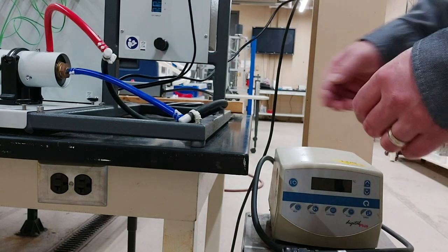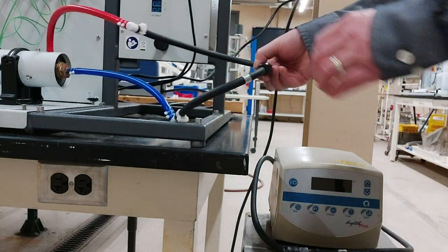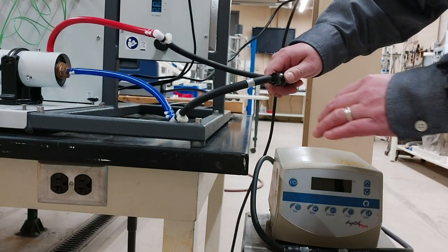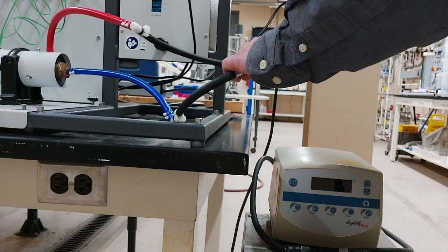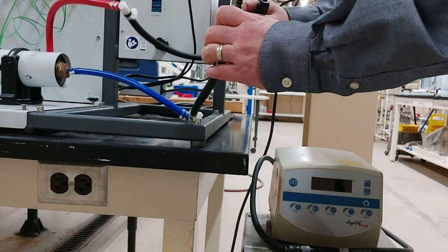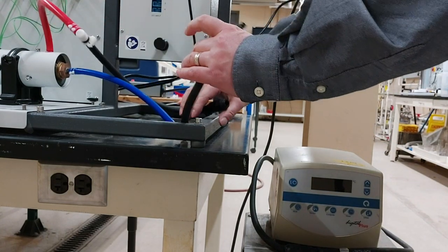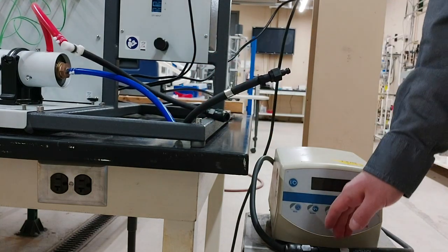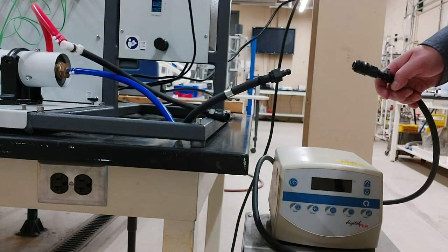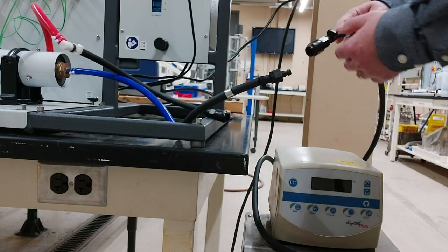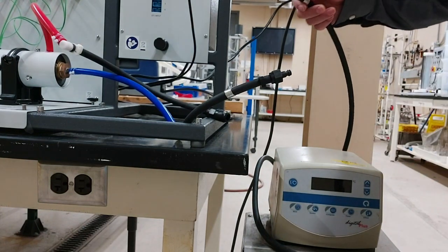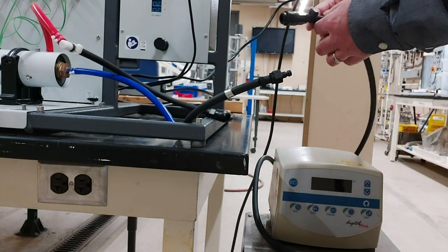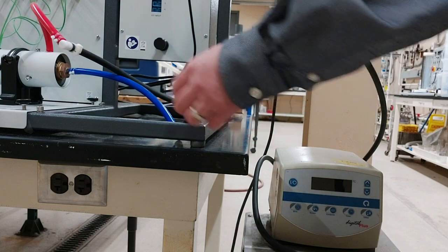Next, you will do the same for the instrument's water tubes. Break the connection of the two water tubes that are currently connected to each other. Then I want you to connect the recirculating chiller's outgoing tube to the instrument's water inlet tube that is connected to the blue tube.